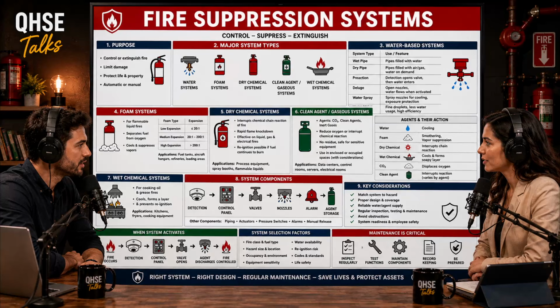Yeah, high expansion. High expansion foam can expand up to 1,000 times its liquid volume. It doesn't look like liquid. It looks like a towering, moving wall of incredibly light soap suds. 1,000 times, wow. You use it to completely fill massive, inaccessible, 3-dimensional volumes, like a deep coal mine shaft or an underground cable vault. It flows around obstacles and suffocates the fire in all 3 dimensions.